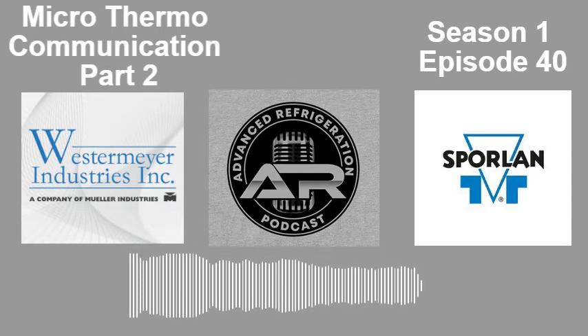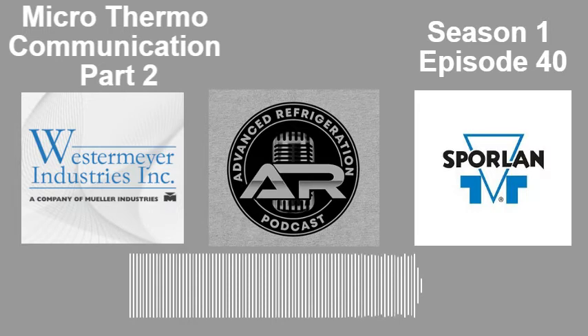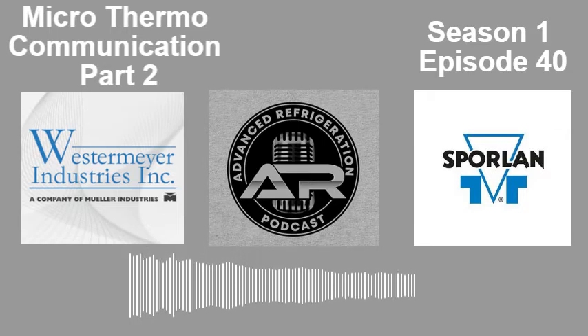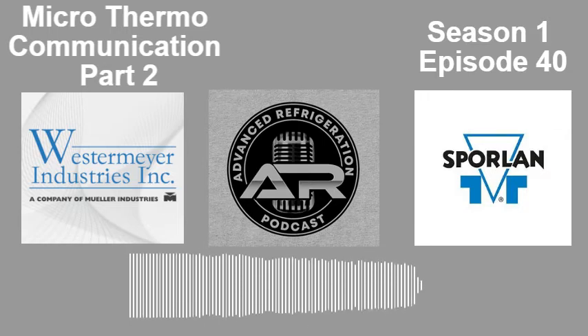Or how about if I had an A8 or A9? So now get this, we make a motorized head that you can retrofit onto an A8 and A9. Back from my days when I was strictly a mechanical guy, I'd do classes and people would ask, wait, which one do I do? Do I do the A8 first, or the A9 first? So to take the mystery out of how you set those valves, you put a motor on the A8 and A9, and then use the 2-valve controller to feather. One is a holdback valve and one is the receiver controller, just to control the receiver in a standard system.